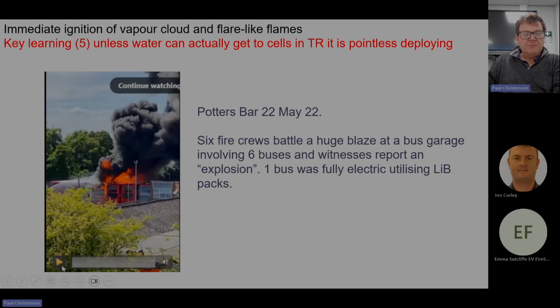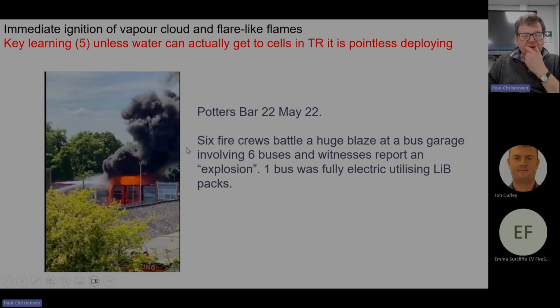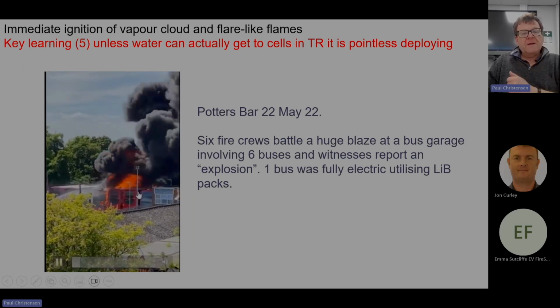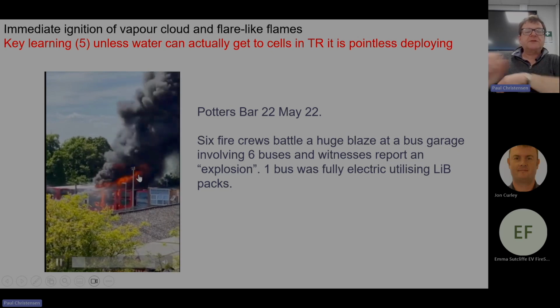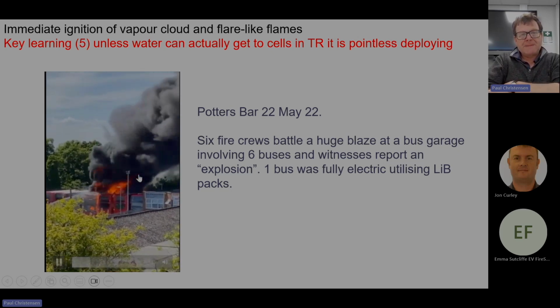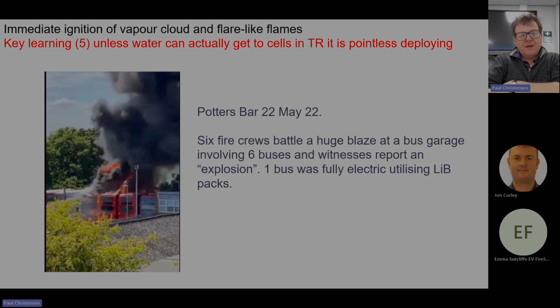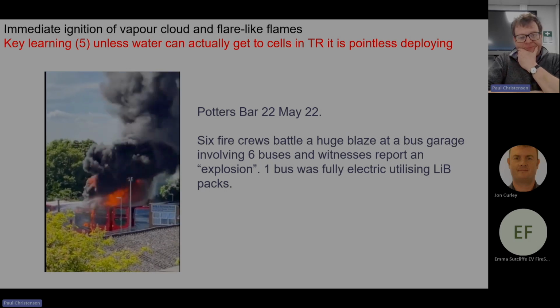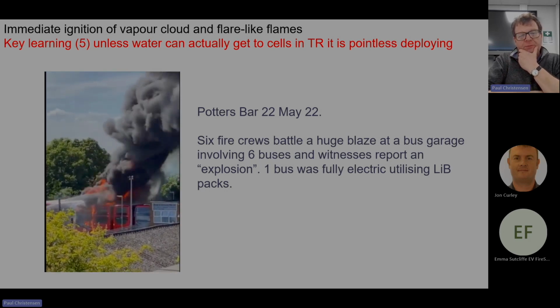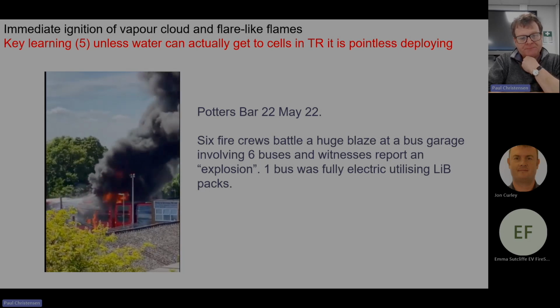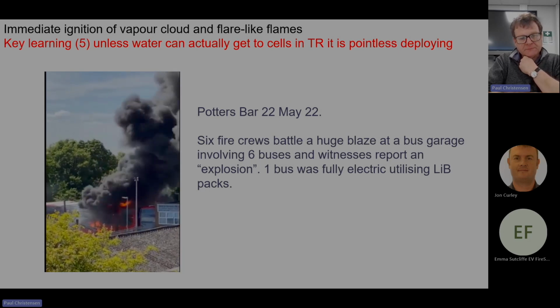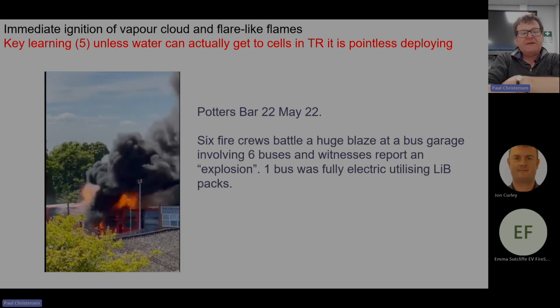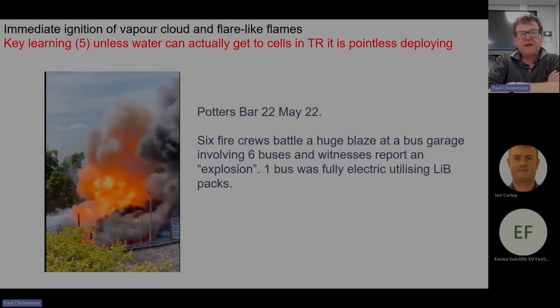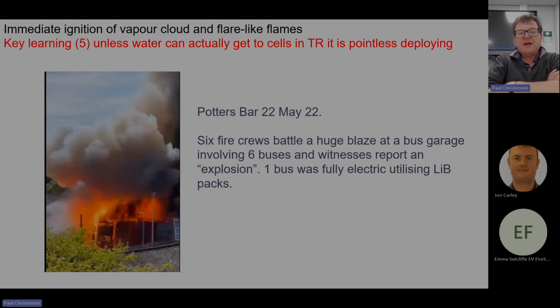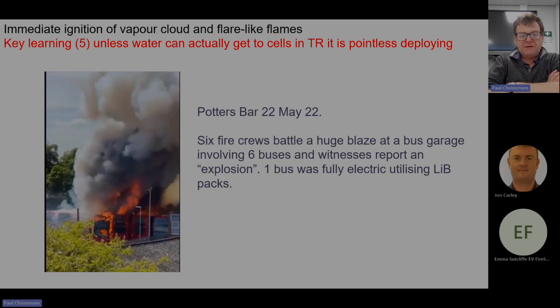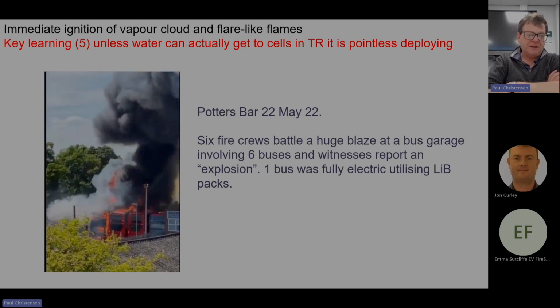This is the Potter's Bar e-bus fire, occurred amongst a load of about 5 other buses. Interestingly, when the water's put onto the batteries, there was an explosion, and you will see that the cells were projected 200 meters, burning. Now, the bottom line here is, unless you can get your suppressant actually to the cells that are in thermal runaway, it's utterly pointless deploying a suppressant.